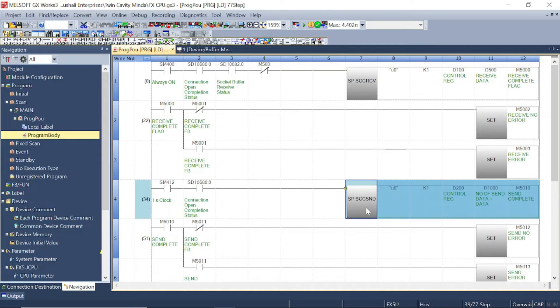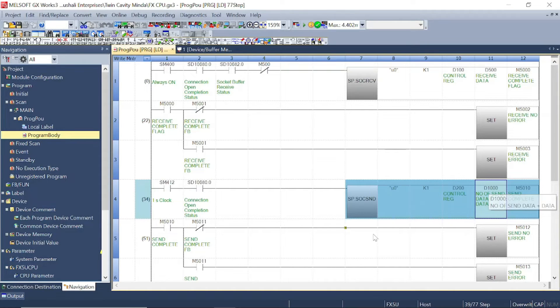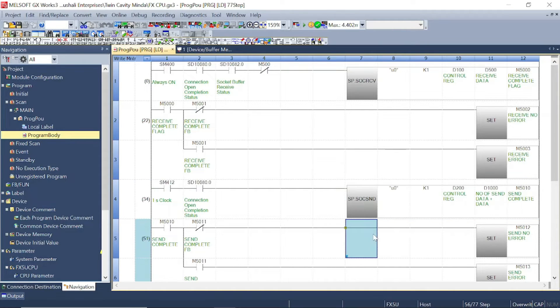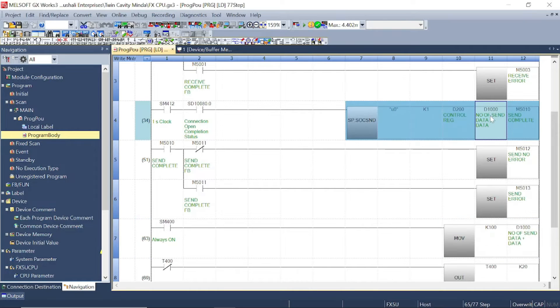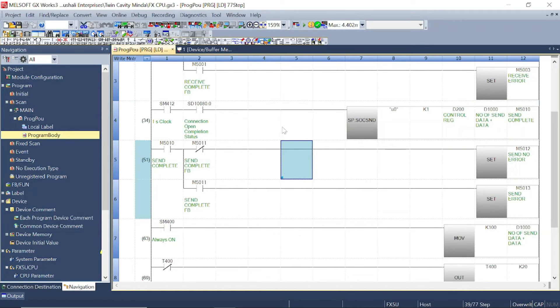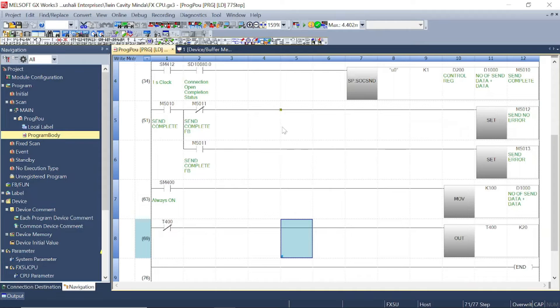This is the socket send instruction for the FX5U. Data in D1000 will be sent to the Q series PLC. From D1000, 100 data will be sent — D1000 to D1099. I have moved 100 into D1000, meaning 100 data will be sent from D1000 to D1099. This is the simple program for the communication.